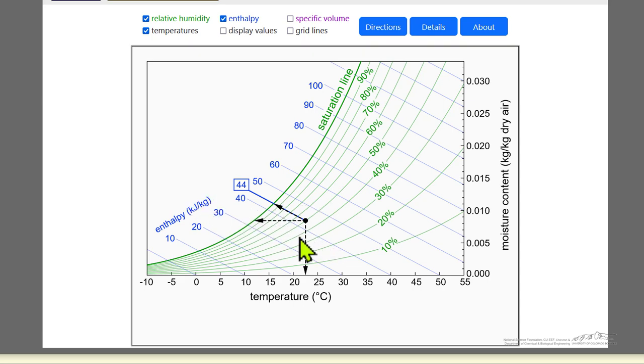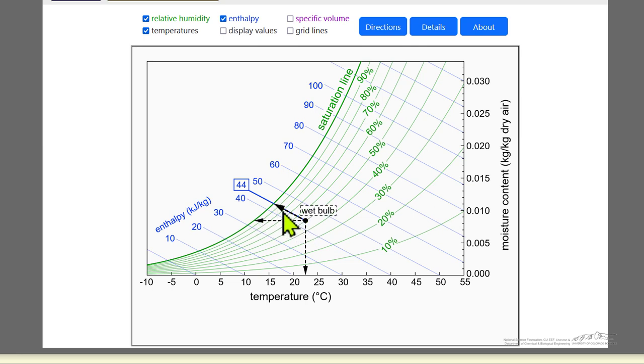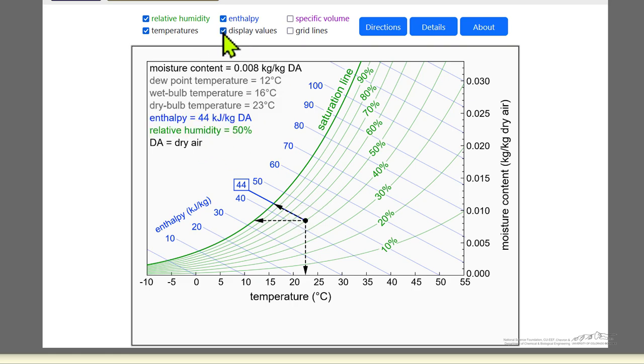Using the mouse, we can see the dry bulb temperature — the temperature that we're measuring — and the wet bulb temperature. Notice this is the line of constant enthalpy. The wet bulb temperature is the temperature where this line of constant enthalpy intersects the saturation line. We can also display these values. The dry bulb temperature is 23, the wet bulb temperature is 16, and this is measured using a wet bulb thermometer.